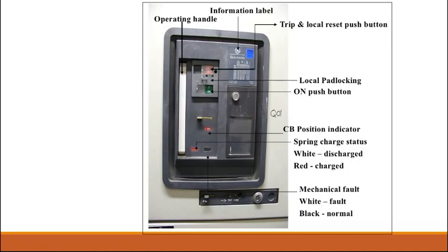Some will give the spring charge indicator either in extended mode or compressive mode. And here is the mechanical fault indicator. If there is any white here, it tells that it is a fault. If it is black, that is the normal condition.